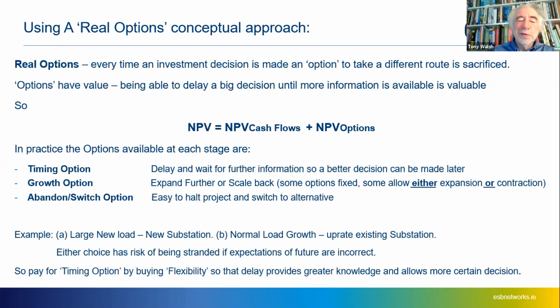A practical example would be a large new customer load that requires a new substation to connect it. That's one option. However, if the large customer load doesn't go on, you just have normal load growth, and you'd only need to uprate the existing substation, which is a different investment. Either choice has the risk of being stranded if your expectations are incorrect. If the new load doesn't come on and you've built a new substation, you never needed to do that—you just needed to uprate the existing one.